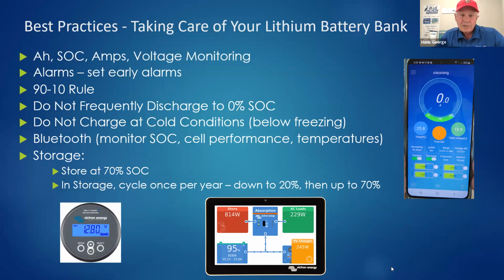Your battery chargers, your battery monitors have alarms in there. If the BMS is going to shut down battery discharge at 10.5 volts, program your monitor, program your chargers to give you a low voltage or a low battery alarm at 11.5 volts. And so you get an early warning. You can go ahead and start charging, start a generator, whatever, to deal with the situation instead of just the BMS shutting everything down. Use these alarms to help you manage your electrical system.